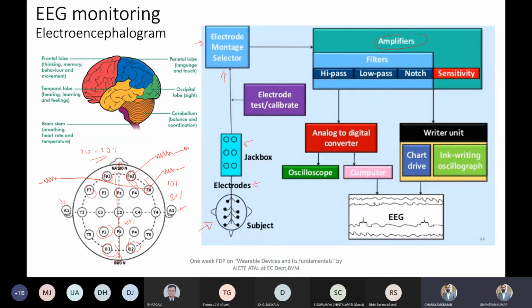In this one, the signals are in microvolts. If you go for ECG, that is in millivolts, but these are very tiny, very low amplitude waveforms. So those are in microvolts, and some high precision amplifiers are needed. Most of the time we use an operational amplifier because its open loop gain is much higher. So those high precision amplifiers are needed to design the circuits. And after that filters are there: high pass, low pass, and a notch filter to remove the 50 Hz noise, and precision and sensitivity all need to be calibrated.